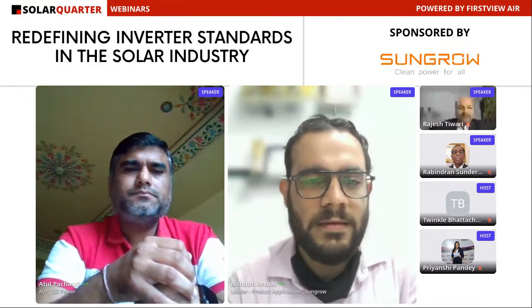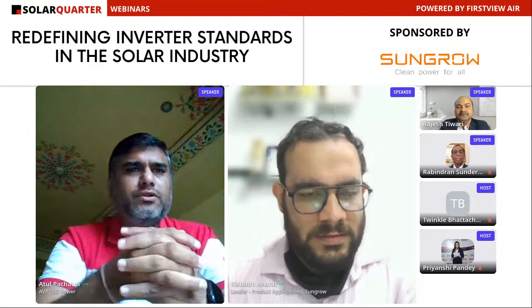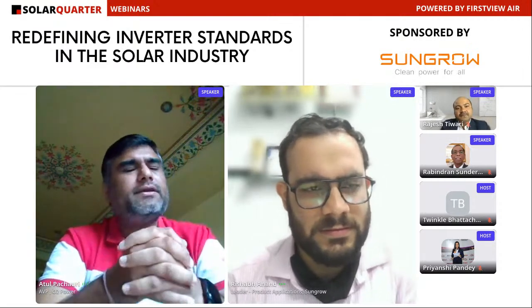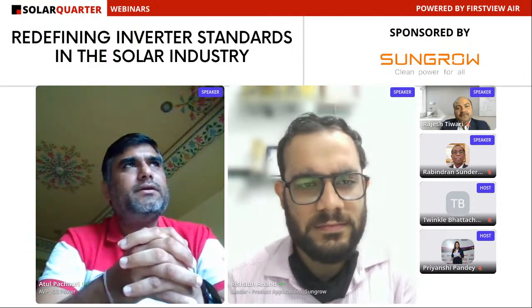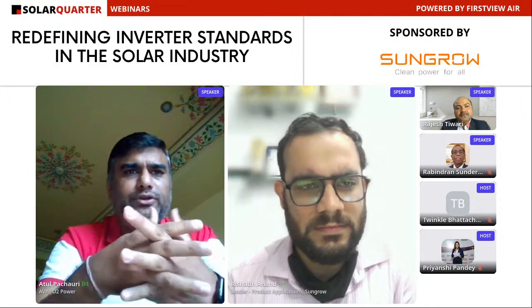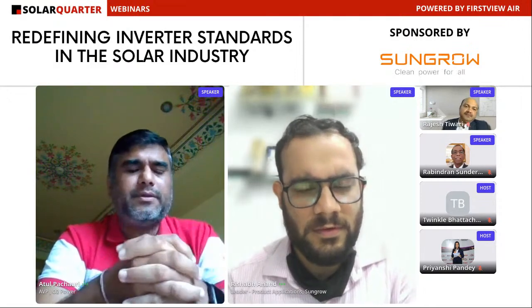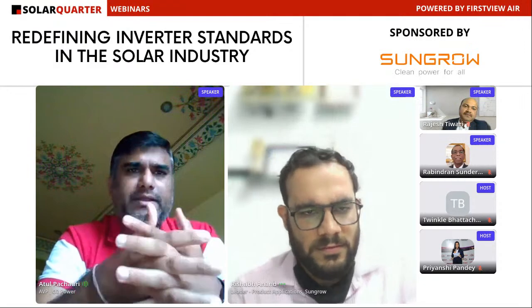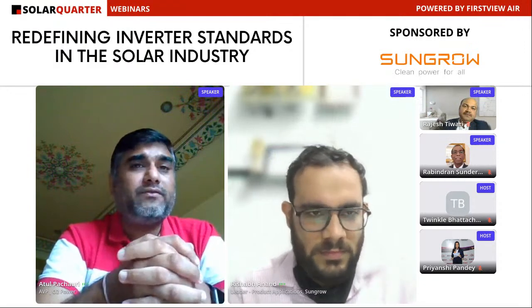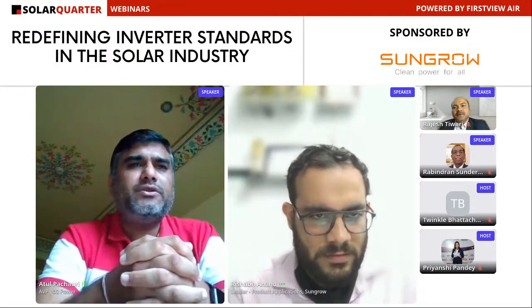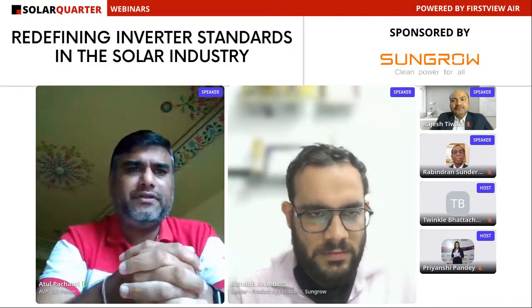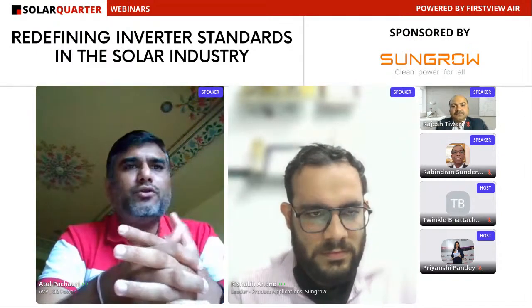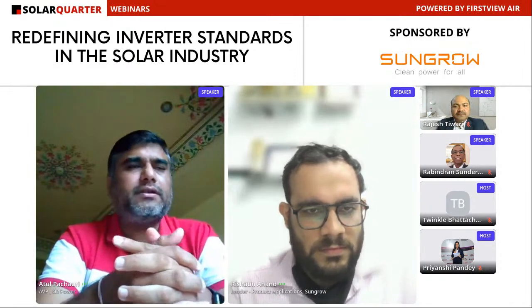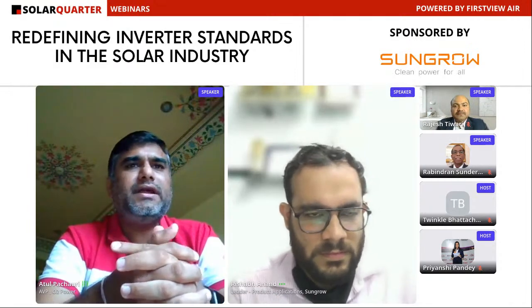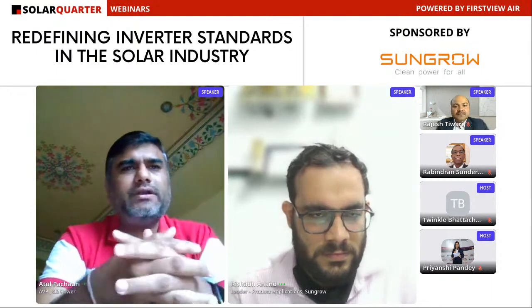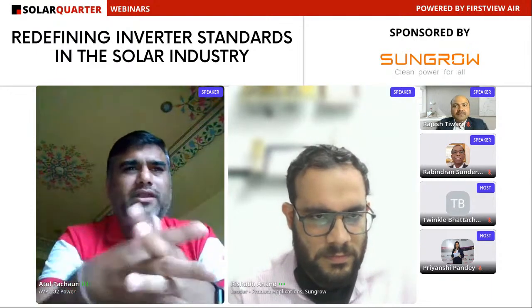Rishabh, practically speaking, when we see the inverter going into degradation mode, it clips the power. Why does it clip? Because the temperature is going beyond the limits. But why is the temperature going beyond the limits? If we have, let's say, 100 inverters in the field, since the ambient temperature is the same for every inverter, we can easily see that a few inverters go into degradation mode while others don't, due to n number of reasons.